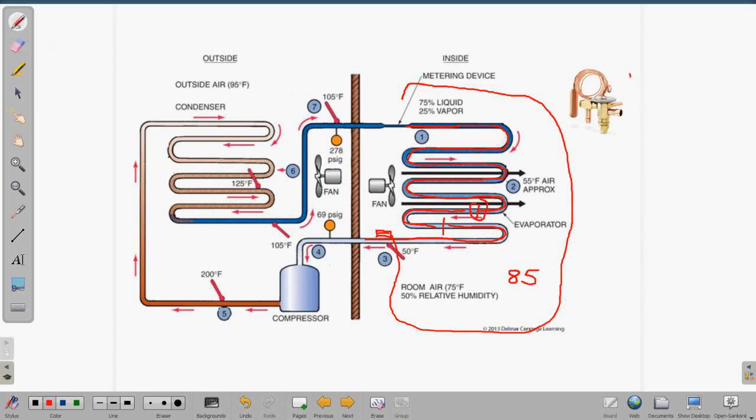And what it does is it pushes that diaphragm down, pushing those push rods down, which opens up the valve, which opens up the size of the orifice, or the size of the valve opens up to allow more refrigerant to flow through.